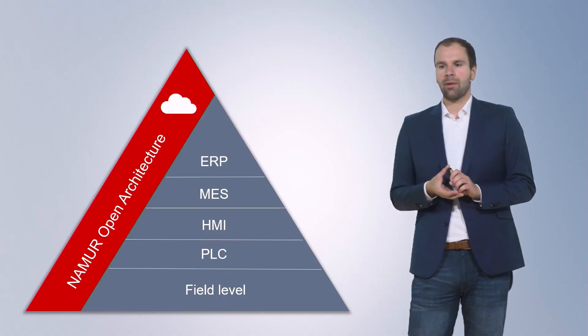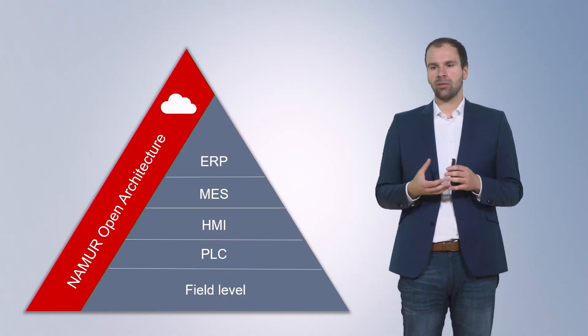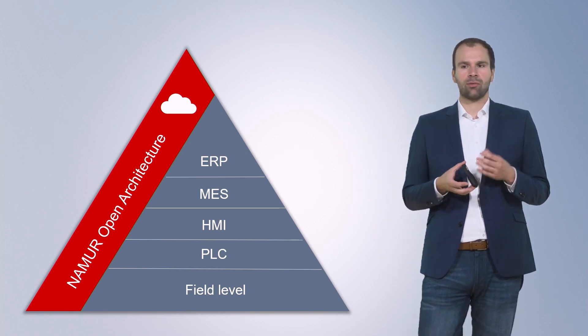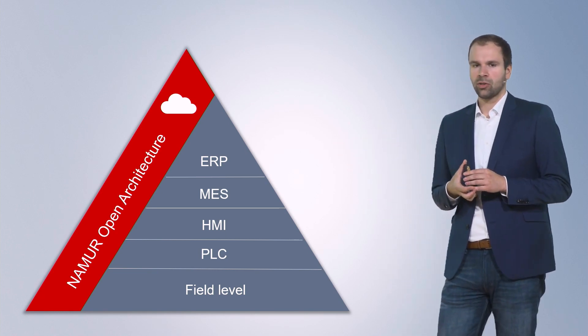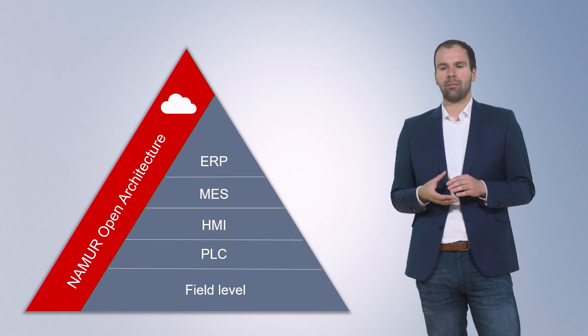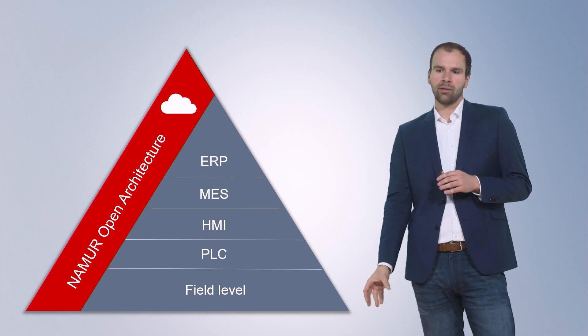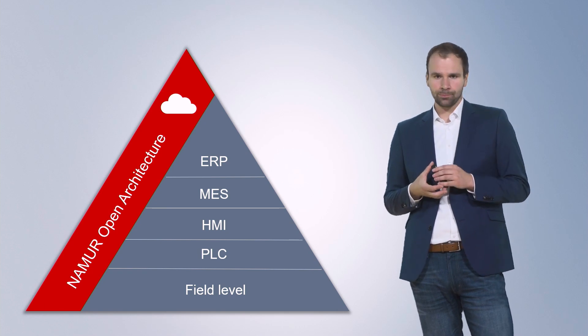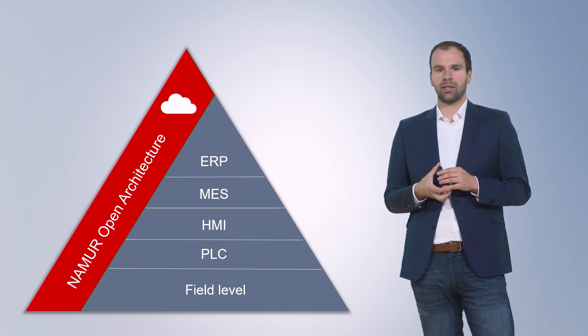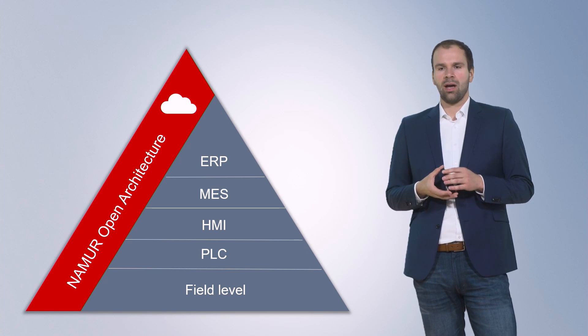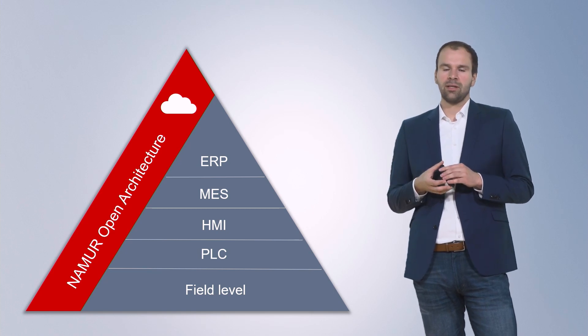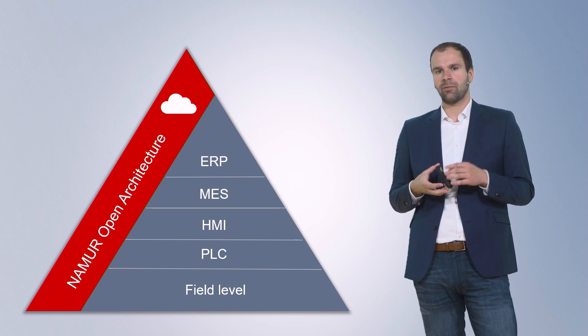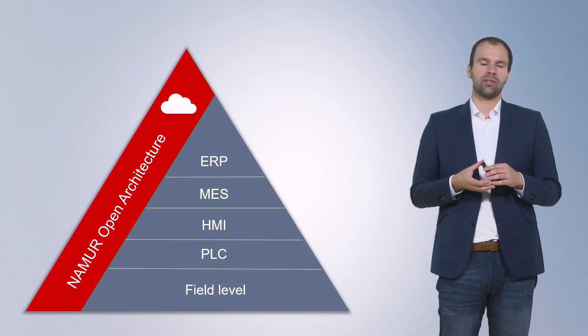So NOA came up with the concept of a second channel — the NOA side channel — which spreads across all the different layers of the automation pyramid, enabling communication from the field level all the way up to all other systems in the automation architecture. Because it bypasses all the other layers, it is independent from them and therefore does not affect existing automation systems.